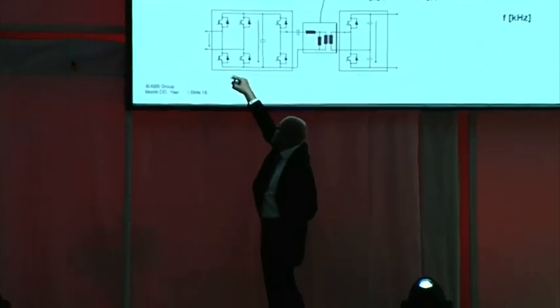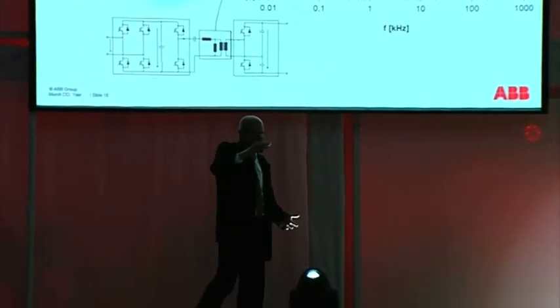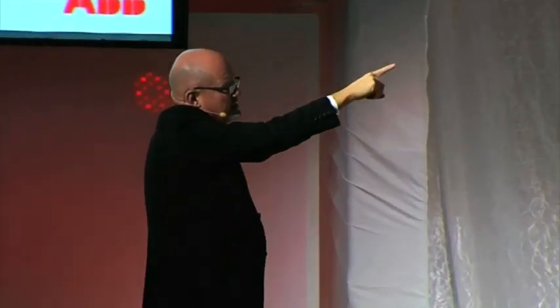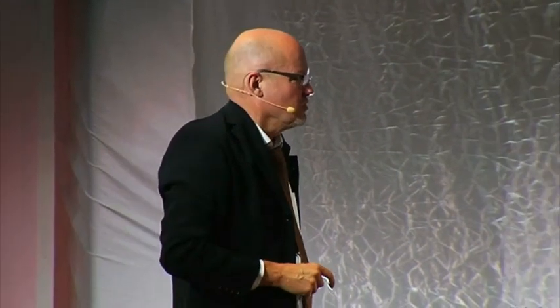So how we do it: we have 9 of these modules. Each module is something like 110 kilowatts in power rating. We connect the inputs here in series in order to take this 15,000 volts AC in, and then the rectifier makes the line current more or less sinusoidal. We have a low voltage, around 1,000 volts, in the DC link capacitor on the left side, and then we have a resonant tank. You see the capacitor, etc. A resonant inverter runs the power through the transformer to the secondary, where we then have the rectifier. The inputs are in series, the secondaries are in parallel.